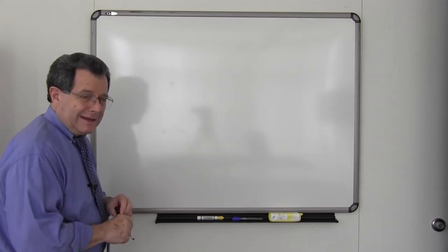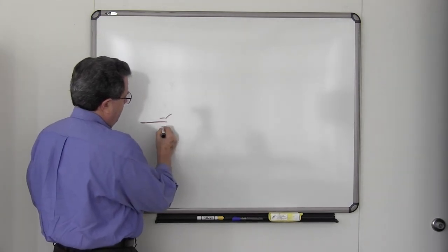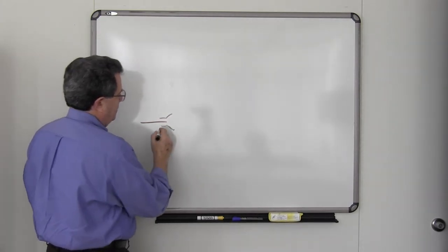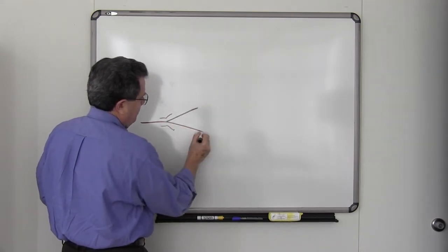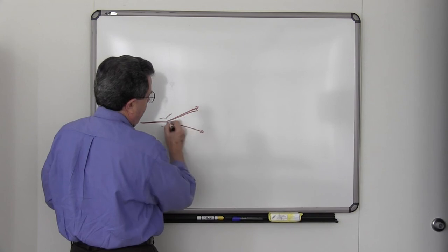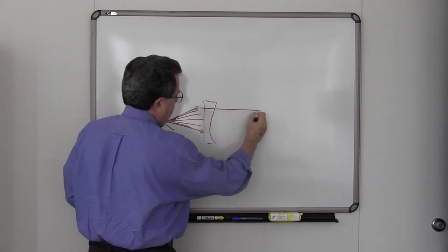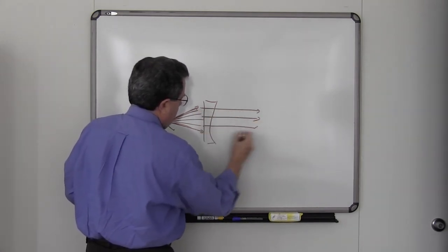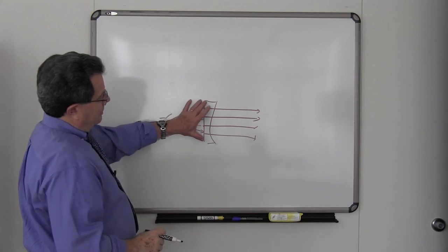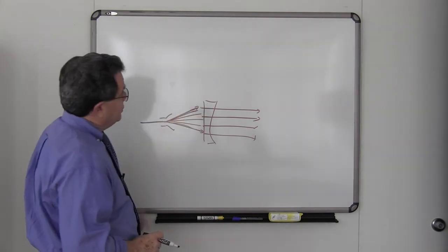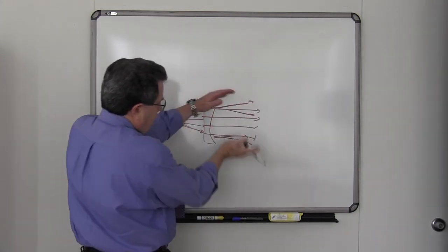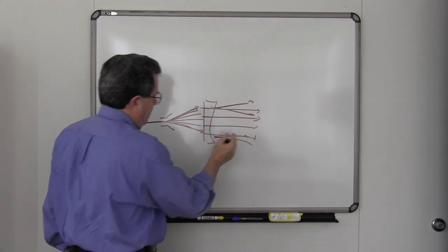On our system, the parallel scan pattern of the beam is produced by an electrostatic parallelizing lens. The unscanned beam enters a pair of horizontal electrostatic deflection plates that produce a fan-shaped pattern of scanned beamlets, which then go through the parallelizing lens and are made parallel. The focusing characteristics of the parallelizing lens can be altered by changing the voltage on the lens, which will produce either overfocusing or underfocusing, and thus can be used to alter the angular characteristics of the beam.